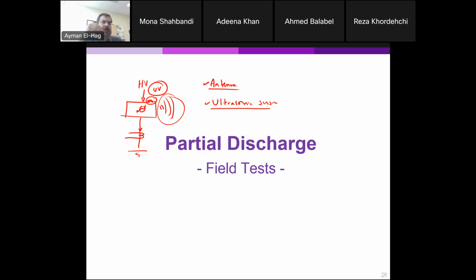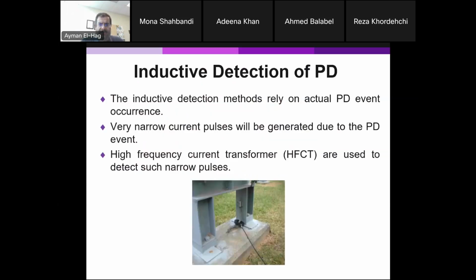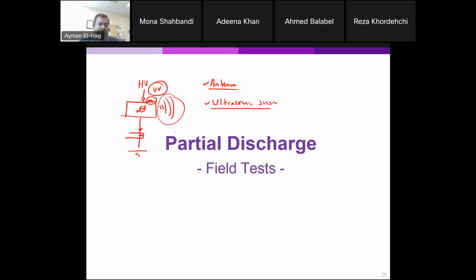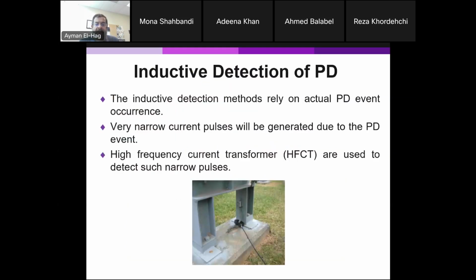Now, we'll go through some of those sensors in more detail: their design parameters, their pros, their cons, limitations, and so on. We'll start with the inductive detection of partial discharge. As I mentioned, there will be partial discharge high frequency pulses going to the ground. The coupling between the discharge that goes to the ground and the sensor happens inductively, meaning that the current will generate a magnetic field around it. So if you have the inductive sensor or current transformer, then you can detect that.